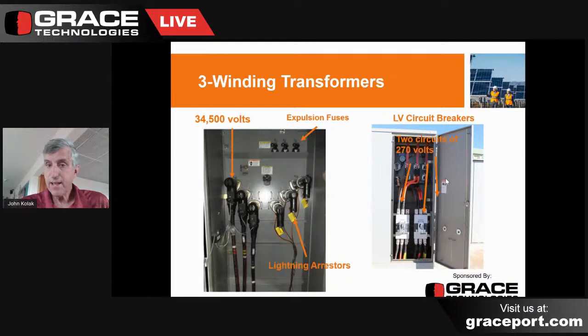On the right side of the slide is the low voltage compartment on the same transformer. Here we have two circuit breakers in there that are internally mounted in the system. In this particular case, they operate at only 270 volts. So the other side of the equation, right? We talked earlier that solar farms can often have systems that run at 900 and some volts or more. 860 volts is a common voltage.